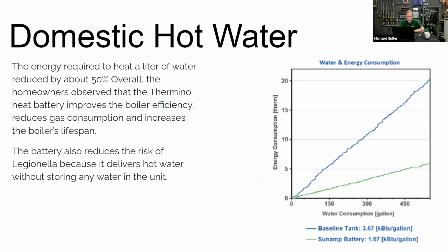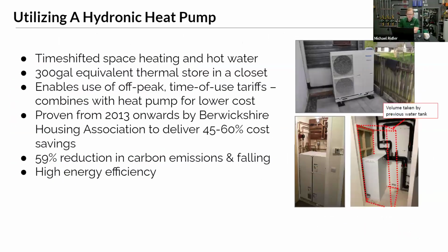The other thing is you'll notice my note about the Legionella. The reason Legionella is not an issue - I'm just going to cut over here - is inside this PCM material is just a small heat exchanger, so the total volume stored in there is basically nothing. It works like a reverse indirect, going from 50 to 140 as soon as you flow through that unit.